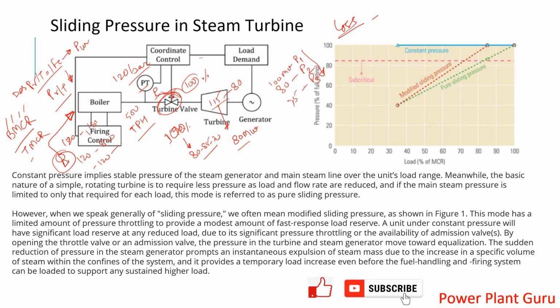So if you change the boiler operating pressure in a reducing way as the load is reducing, then you can reduce the discharge pressure. You can maneuver the boiler feed pump also to have a lower discharge pressure. By that, you are reducing the work done by this pump. So ultimately, here also you are reducing your losses, and here also you are improving on the energy consumed by the boiler feed pump. So those two things are making your system more efficient.